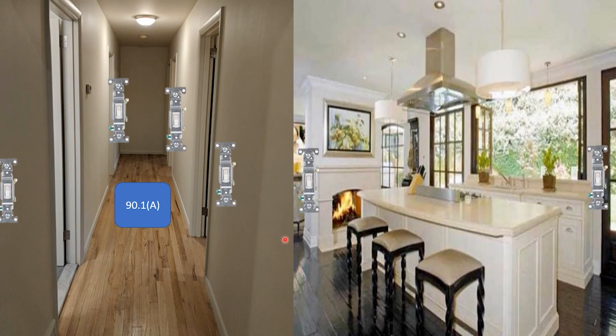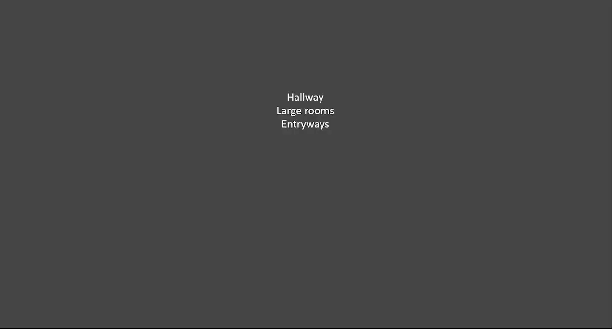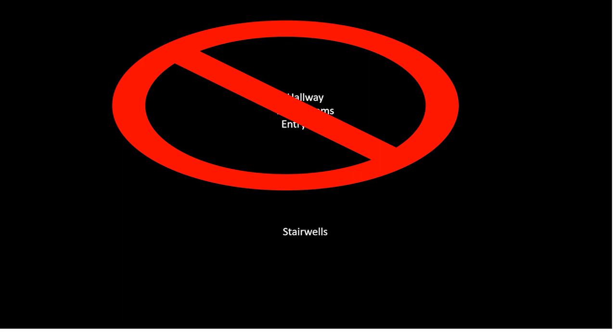There is one place in the code, though, where it does specifically require three-way switching, and it might surprise you. Of all the places that the NEC could require three-way switching configurations — hallways, large rooms, entryways — unfortunately, it's not any of these. The only code-required place in the NEC where you have to have a three-way switching configuration is going to be in stairwells.